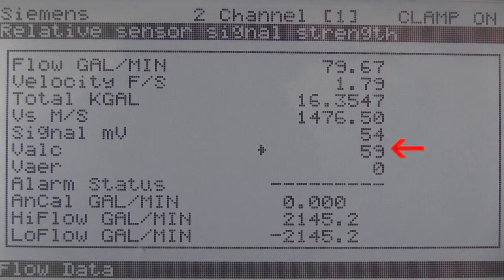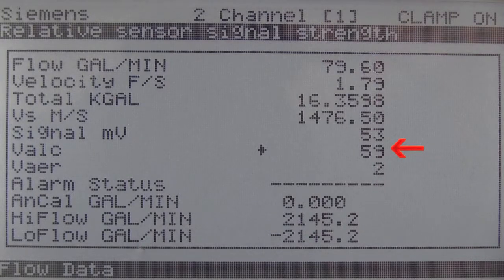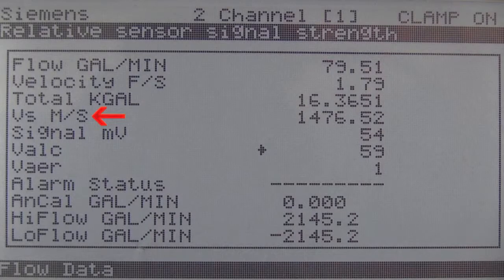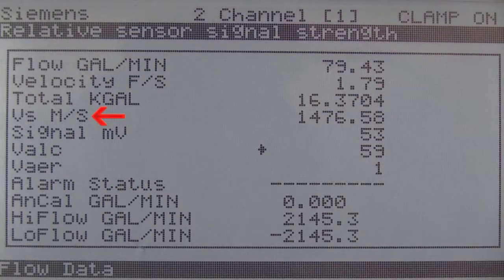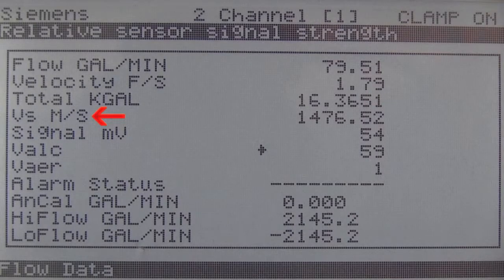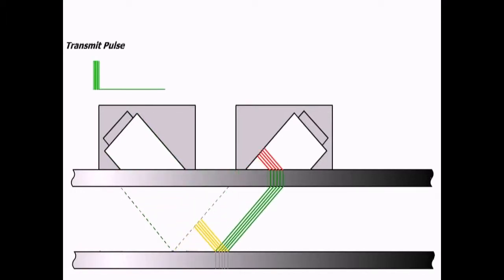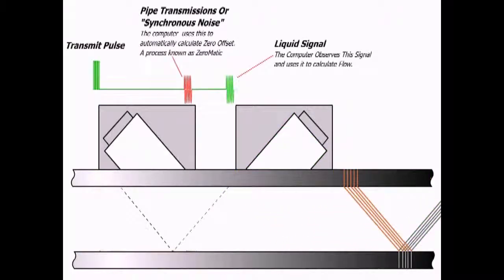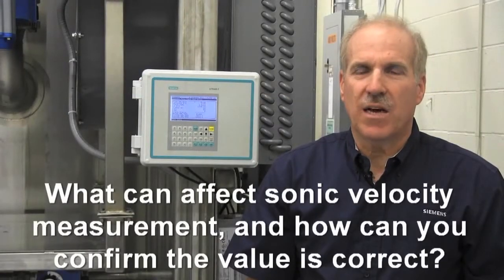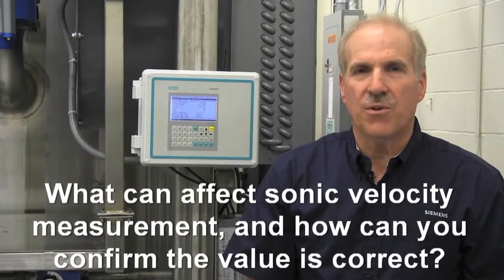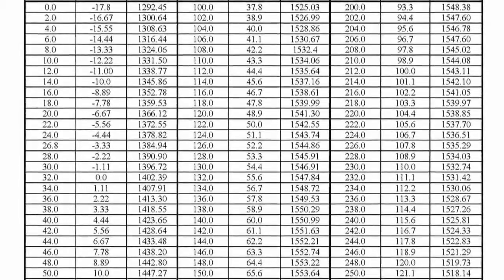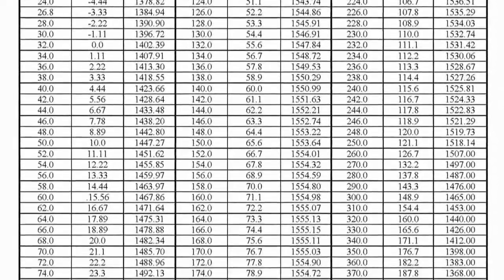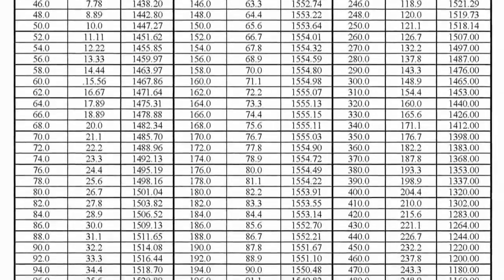So having confirmed adequate signal strength, let's revisit the sonic velocity measurement indicated by the parameter VS. This is the same value that was presented at the conclusion of the installation process and is the key indicator of an accurately performing meter. VS is precisely computed from the transit time measurement. Its value enables the meter to determine the refraction angle of the sonic beam in your liquid and is therefore a fundamental part of the flow equation. What can affect sonic velocity measurement and how can you be sure the displayed value is correct for your liquid? The main influences on sonic velocity of a fluid are its temperature and density. Let's take the example of water. Siemens has a very detailed table of water's VS relative to temperature. Therefore, it is very easy to determine what your sonic velocity should be based on your water temperature.